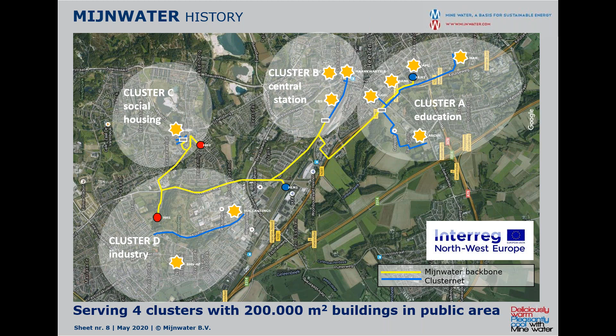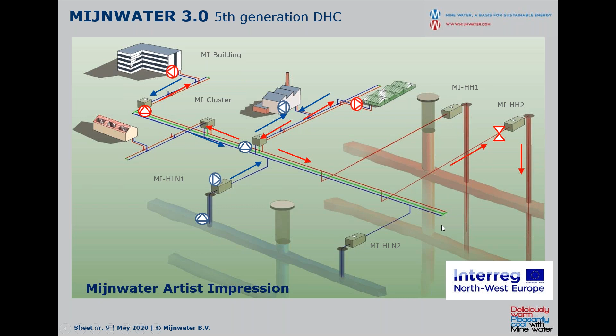Here's the idea: if a building connected to this cluster grid needs cold, its pump starts running and takes cold from the cold pipe, re-injecting heat into the hot pipe. If there is a building in the same cluster that needs heat, its pump also starts running, and automatically heat flows from one building to the other. If there is a net heat or cooling demand in the cluster, it goes to the cluster basement and exchanges this energy with the backbone. Since we now have 4 cluster basements, it first checks if there is complementary energy demand from another cluster. If not, we go all the way back to the mine and store it in the mine reservoir.